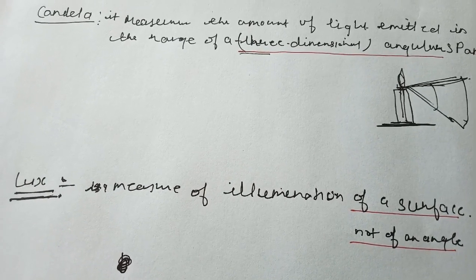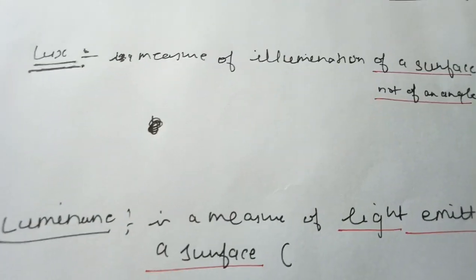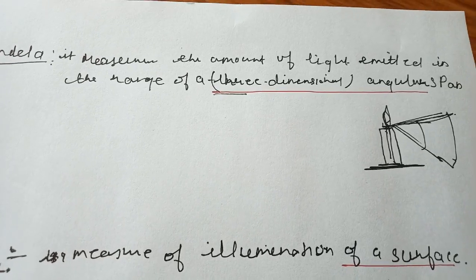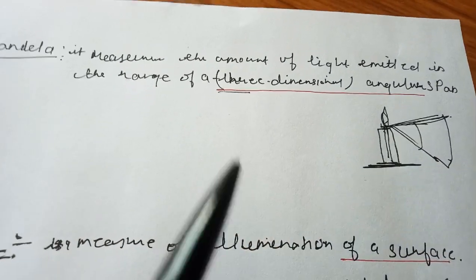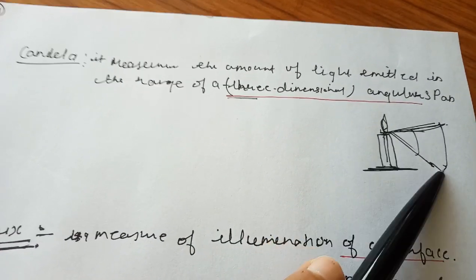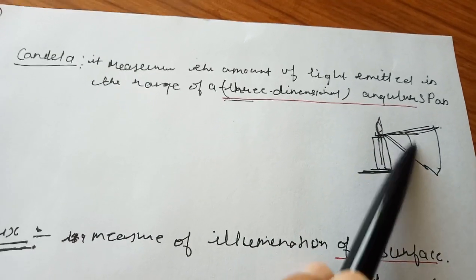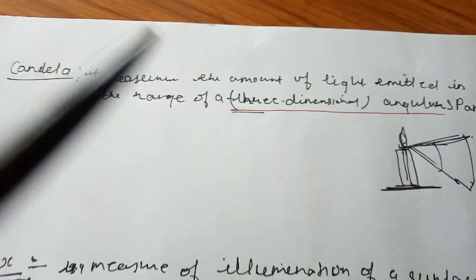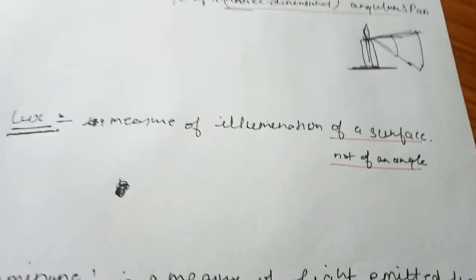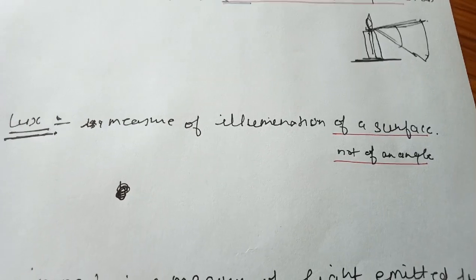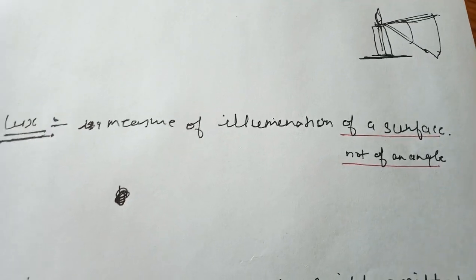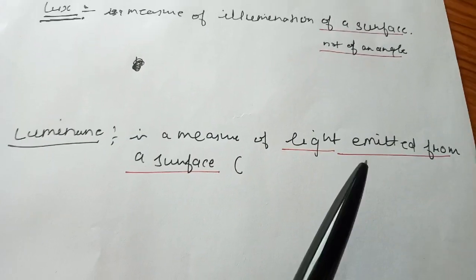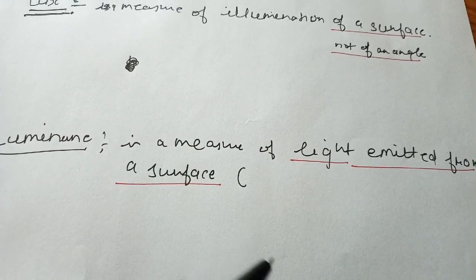Now we discuss the key terms: candela, lux, and luminance. Candela measures the amount of light emitted in a three-dimensional angular span — it is the measure of luminous intensity in a particular direction. Lux is a measure of illumination of a surface — the total illumination across a surface in all directions. Luminance is the measure of light emitted from a surface, measured in candela per square meter.